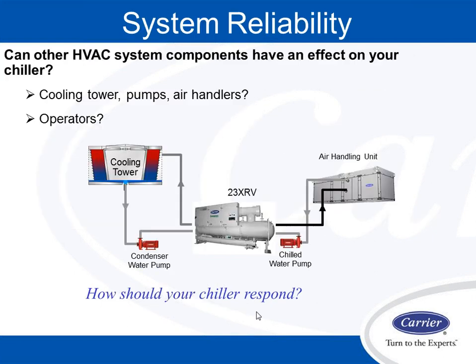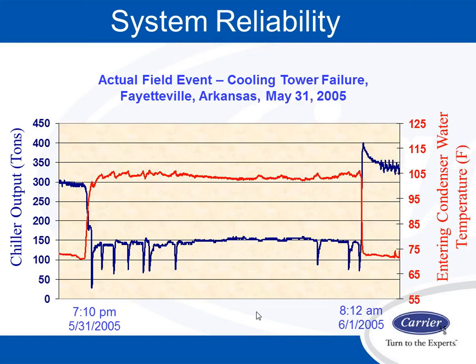So we look at this design here and say, I have very little, I have no redundancy built into this. So I have a cooling tower, a condenser pump, the 23XRV, a chilled water pump, and an air handler. What happens if something happens to one of those components? As you saw in the video, we have a snapshot. This was one of the first beta sites that Carrier had. They had a machine running at 300 tons, shown in blue, with around 72-degree entering condenser water.